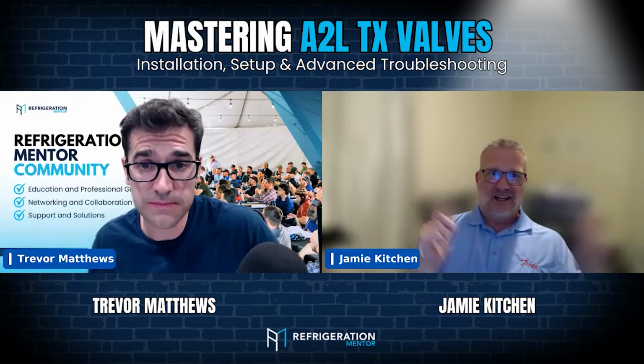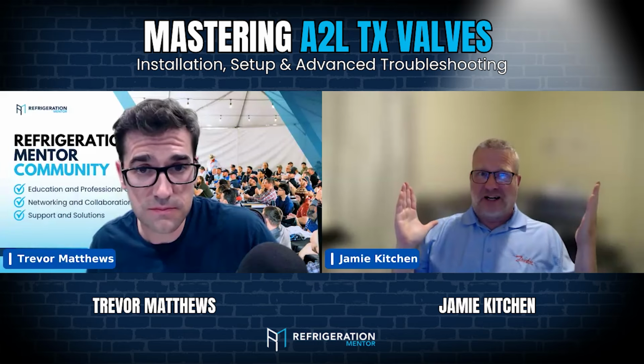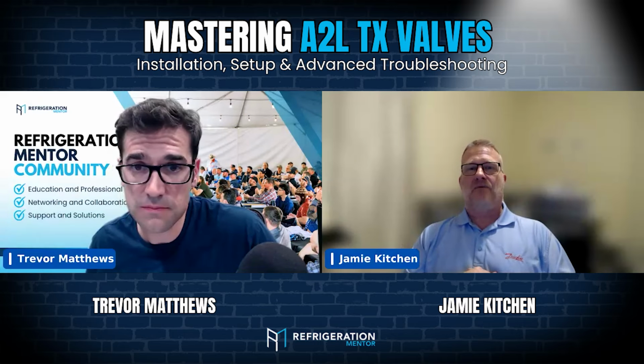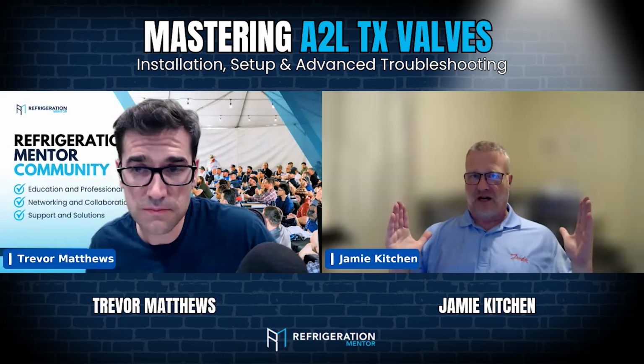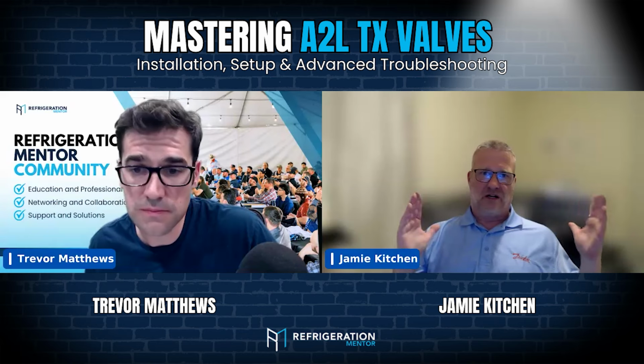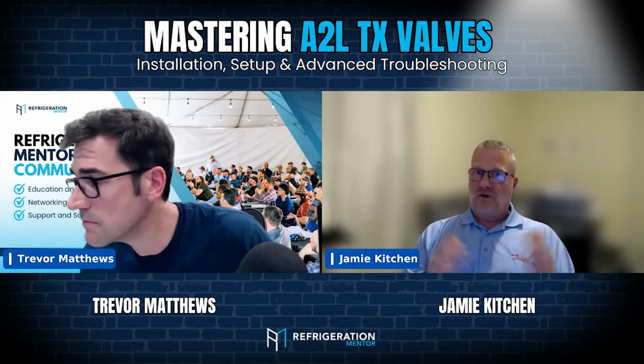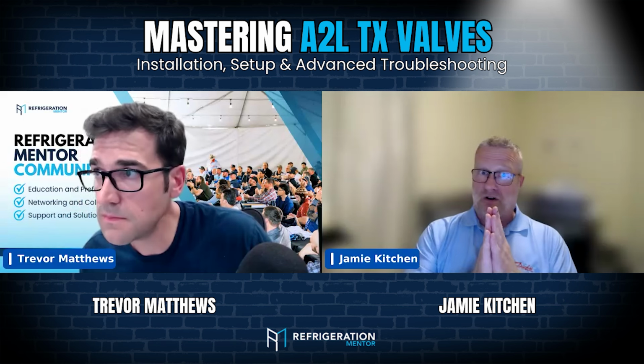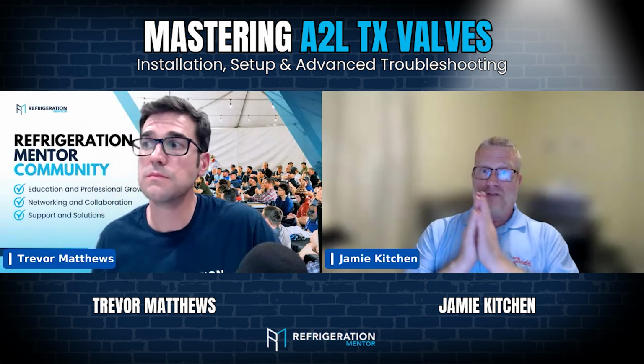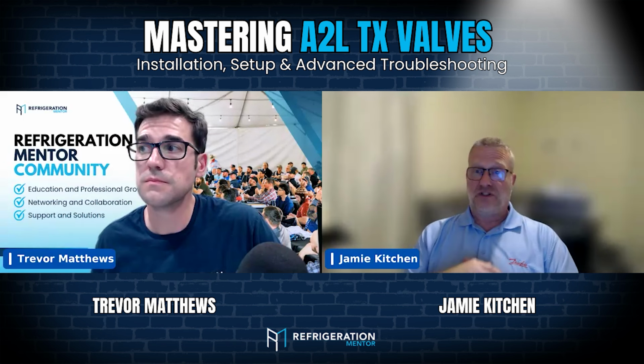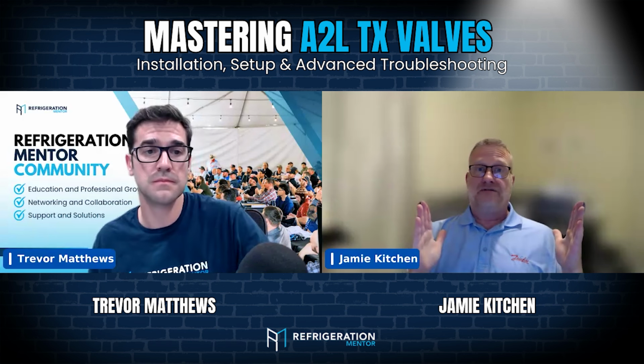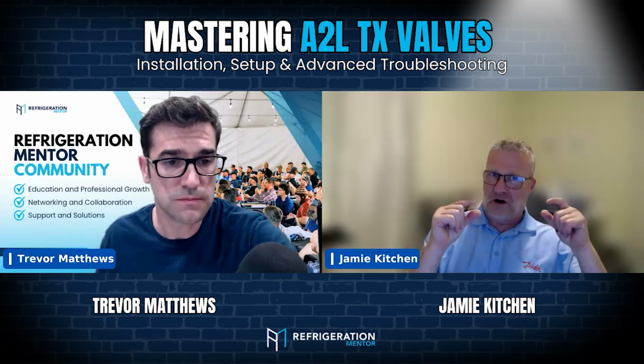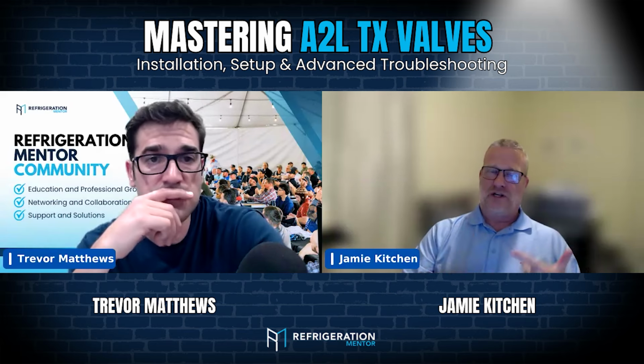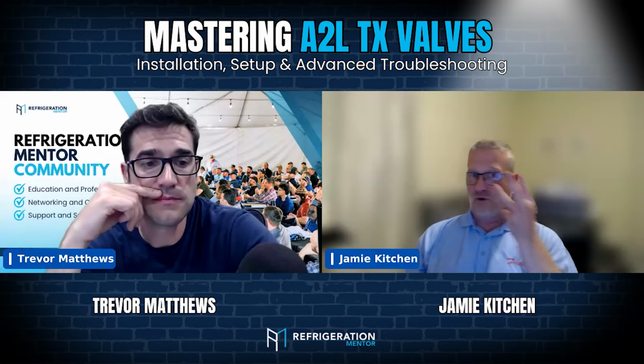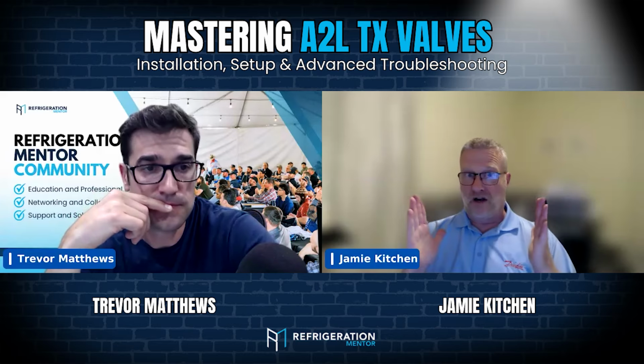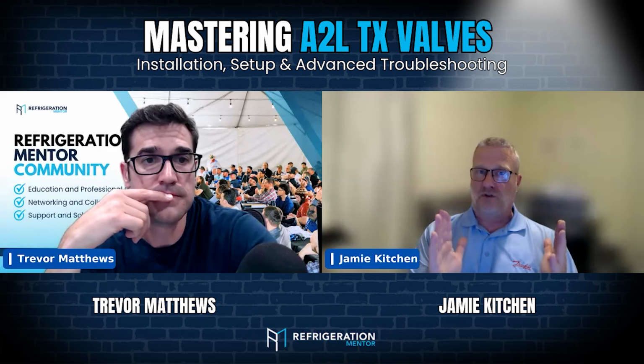Let's talk. Not to pay the bills, but we kind of got to pay the bills here. We basically have what we call a universal aftermarket valve. If we talk about the TR6 valve, we're introducing that for the wholesaler and for the contractor. That's what you see here. The valve has the magic sauce in the bulb. It allows you to work with R32, 410A, and 454B, all with one valve. So it services all three of those systems.